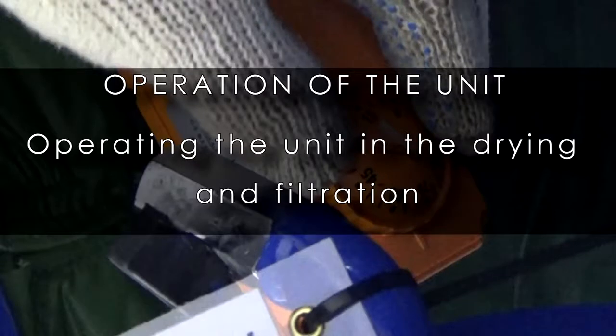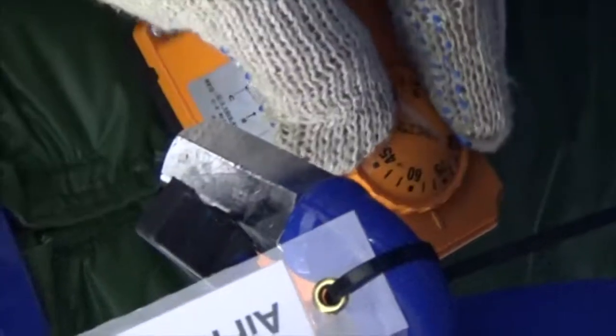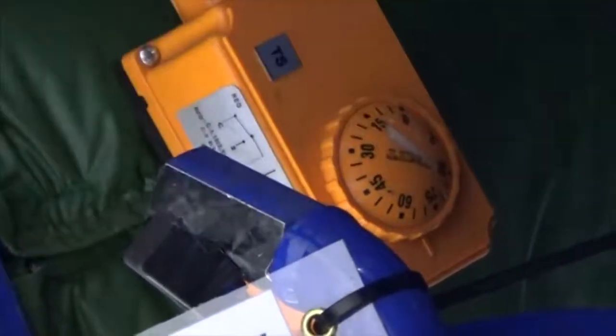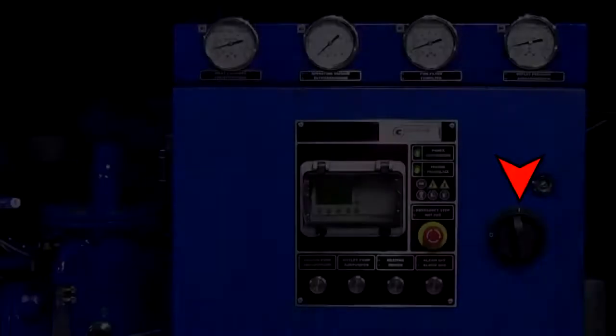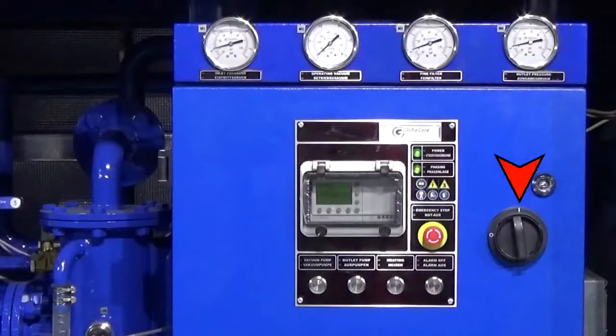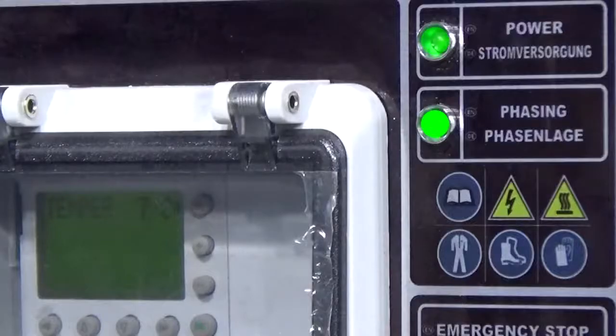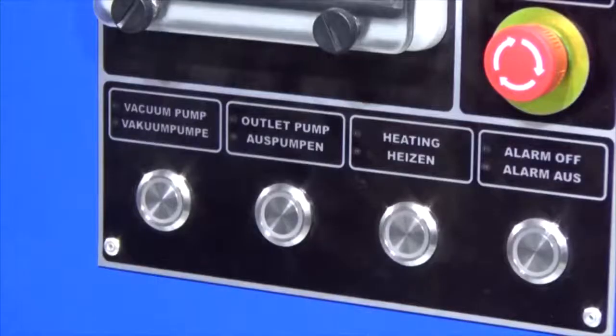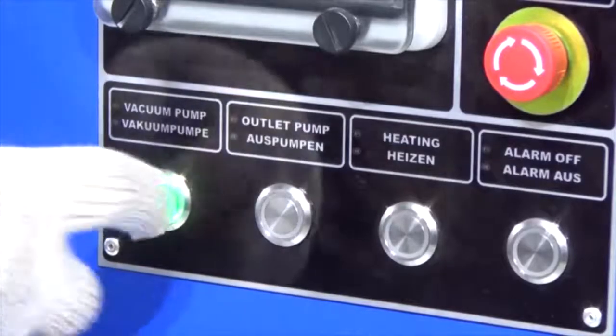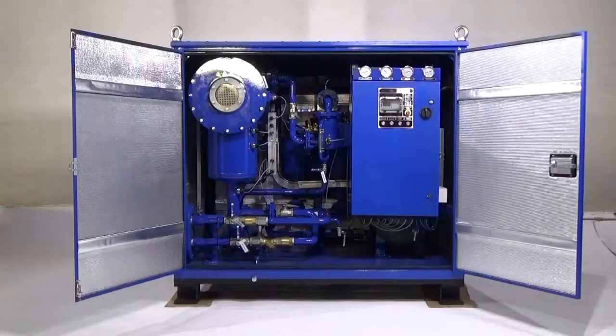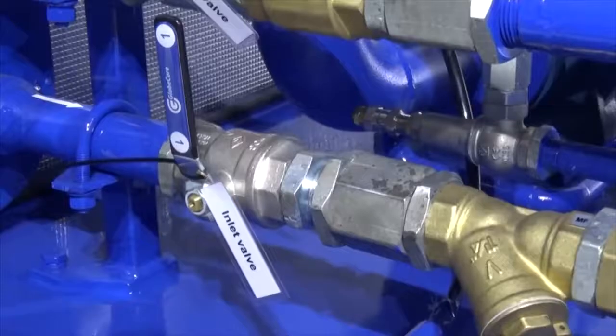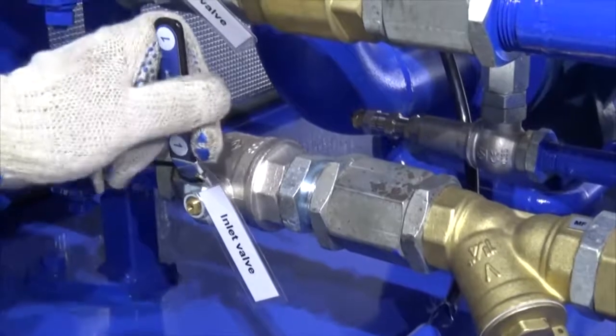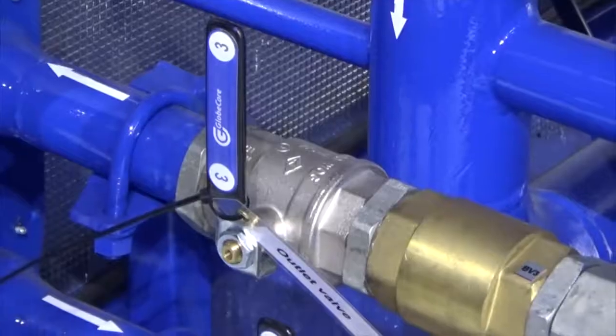Operation of the unit. Operating the unit in the drying and filtration mode. 1. Set the thermostat to the 70°C mark. 2. Power the unit by turning the power handle to the on position. Power and phasing lights must be on. 3. Start the vacuum pump by pressing the vacuum pump button. 4. Open valves MV1, MV3, and MV5.